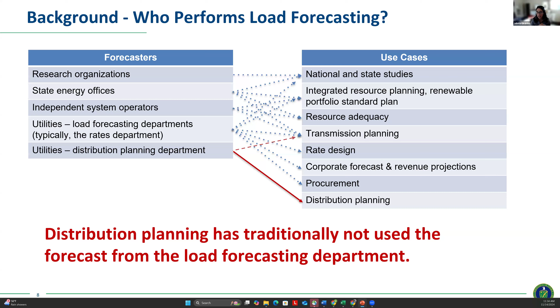Load forecasting departments and ISOs typically forecast energy and coincident peak demand, so system-level peak demand, maybe for a service territory, an entire ISO, or a state. But that has been really hard to apply to the local area. So distribution planning has simply come up with their own non-coincident peak loads, since a feeder might not peak at the same time as the system peak. The need is typically at the substation or feeder level, to determine if the infrastructure is big enough now and will be big enough in the future.